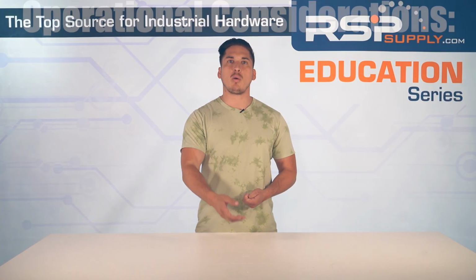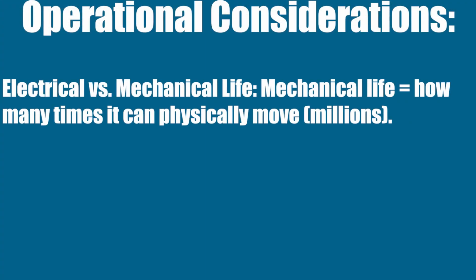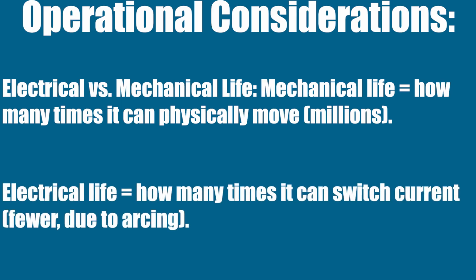Operational considerations, things to think about as you operate this equipment. Contactors don't last forever. Here's what wears them out. Electrical versus mechanical life. So you have mechanical life, how many times it can physically move, in the millions, or electrical life, which is measured by how many times it can switch current, which is going to be fewer than the mechanical due to arcing.